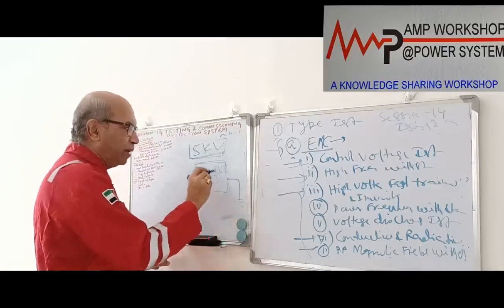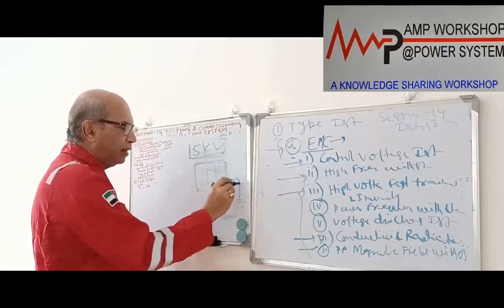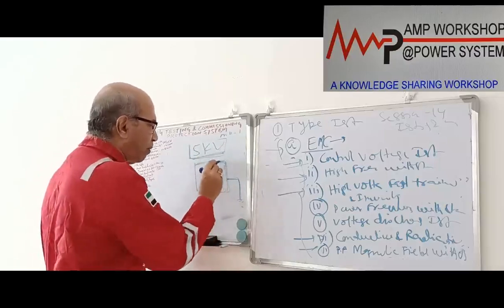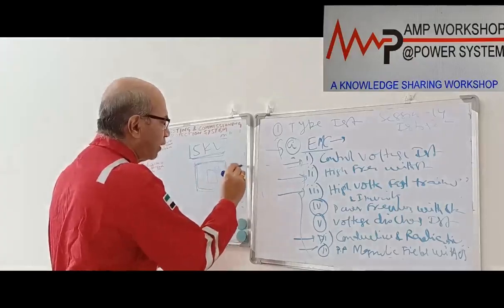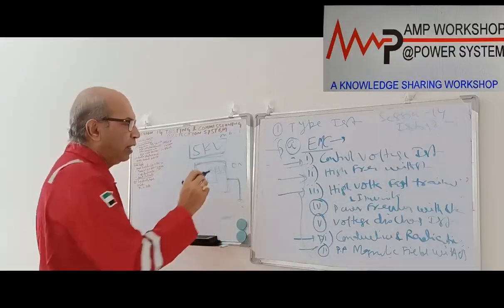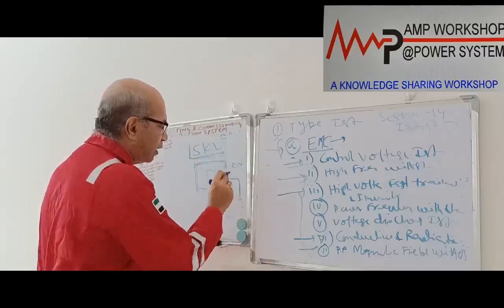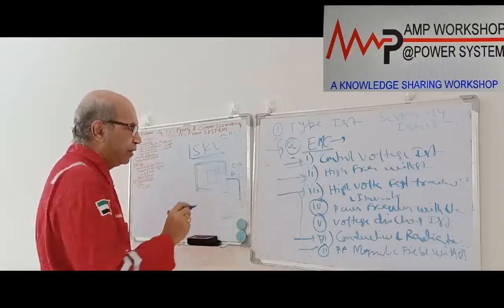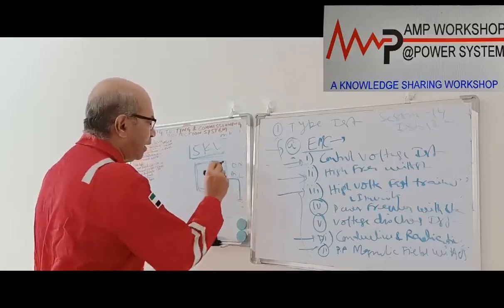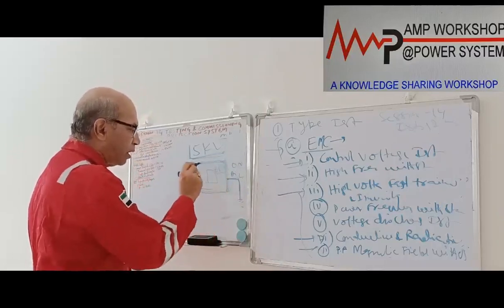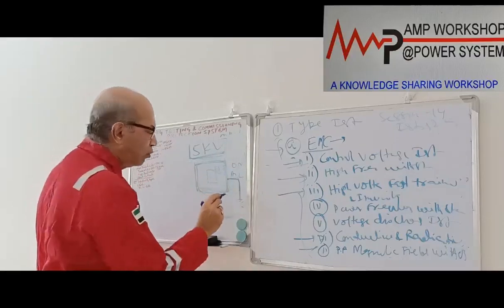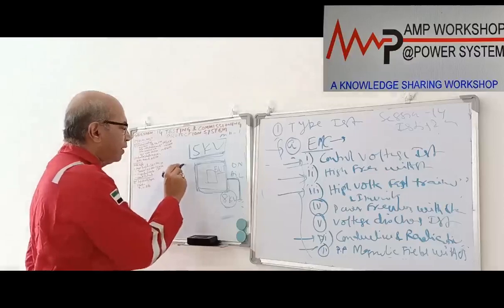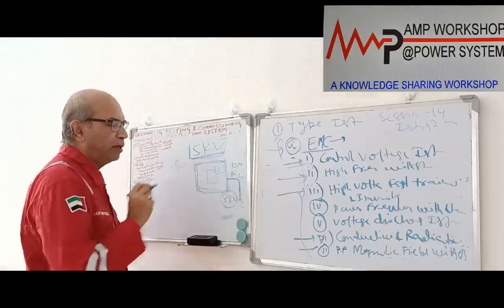Okay. So if it is a conductive cover, then this test is 15 kV we do for the air discharge. Suppose the cover is insulated and the cover is on, in the body with the relay body. In that case, 15 kV we charge it, and through the air discharge we discharge it. During the discharge the relay should not maloperate. But if it is in the on condition and the cover is a conductive cover, in that case we do the test at 8 kV. So the conductive test will be 8 kV. We charge the plate with 8 kV and then we discharge it.